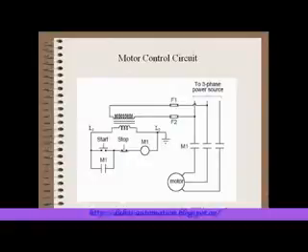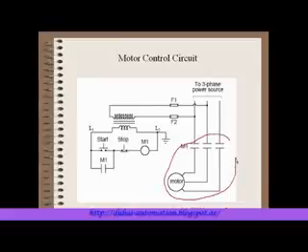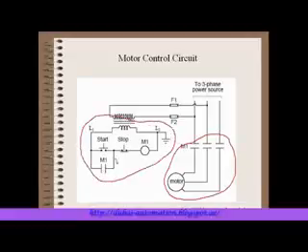Okay, let's stop for a second and maybe step a little bit back outside the PLC and talk about what's really happening and what you're doing. What we have here is a standard motor control circuit. You have a three-phase motor right here, and you have your control circuit over on this side. Now you have your start push button, you have a stop push button, and then you have a typical relay with a seal-in contactor where when that relay pulls in, it actually seals around this momentary start push button. So that's our standard motor start-stop circuit that we have for a PLC.